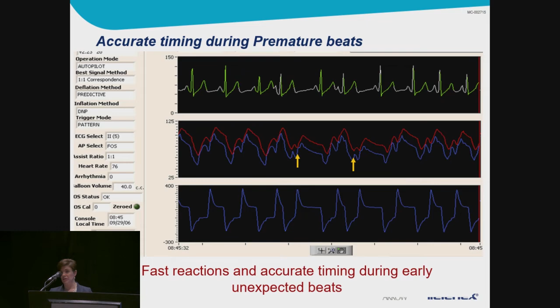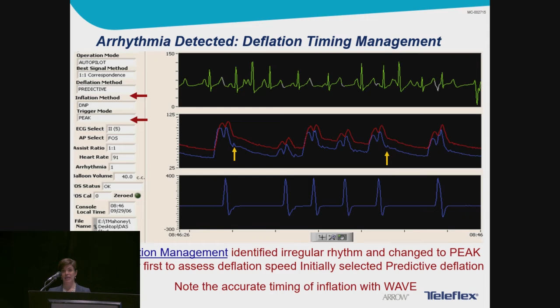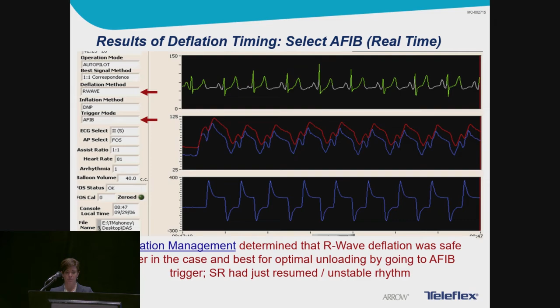This slide shows the fast reactions and acute and accurate timing during early unexpected beats, a normal scenario that we see all the time. Here you can see that the patient's rhythm actually went irregular, and the pump began the deflation timing management program to determine if there was enough time to deflate the balloon on the R wave or not. This program compares the Arrow system's balloon deflation speed to the time available to deflate the balloon. When 70% of the balloon volume can be removed prior to the next systole, R wave deflation can be selected. Here you can see deflation timing management determined that the R wave was acceptable and AFib trigger was selected, and the patient did go back into a regular rhythm. However, the pump did continue on with that trigger because it was safe for the patient.